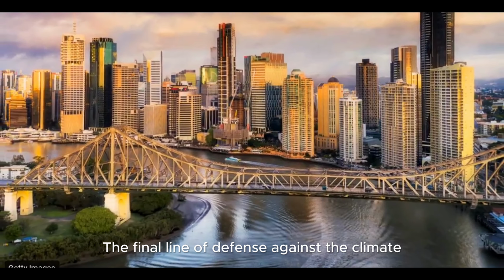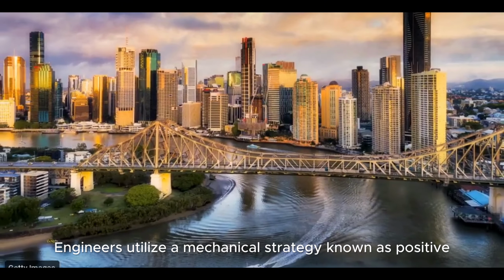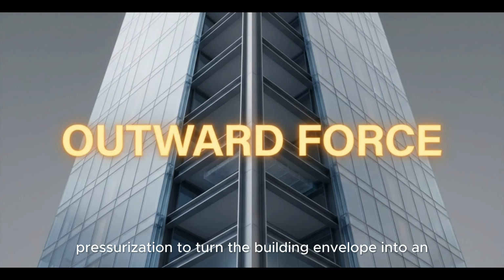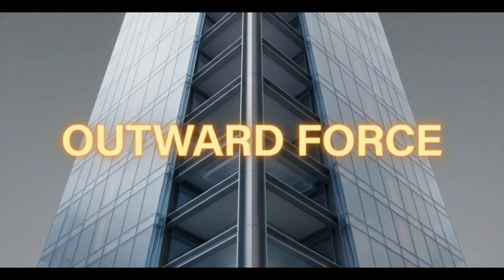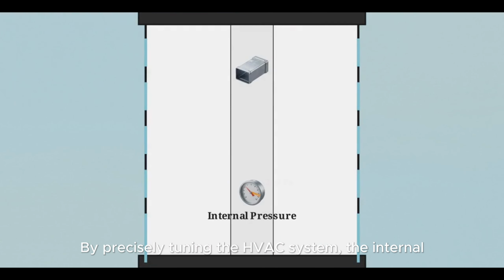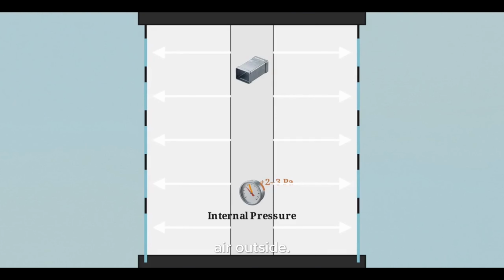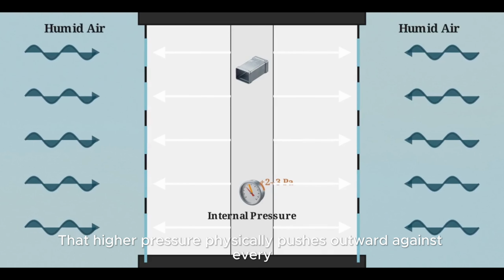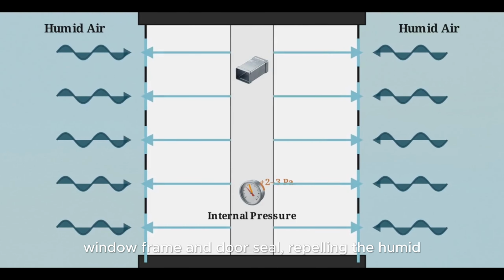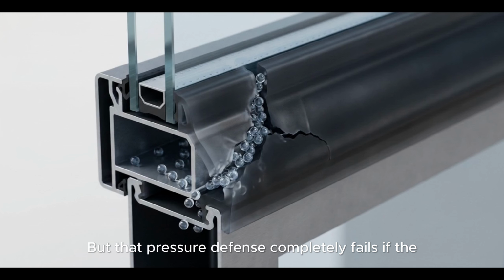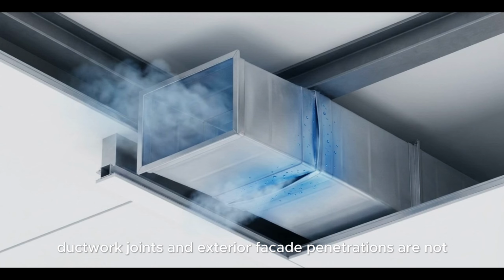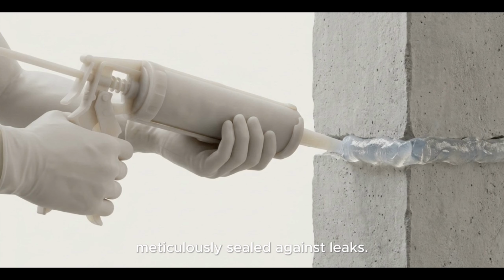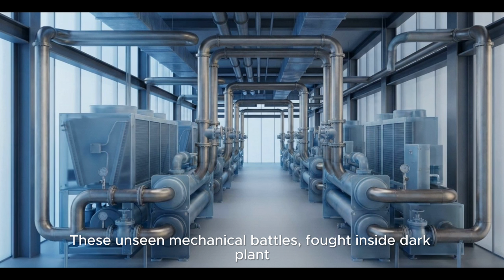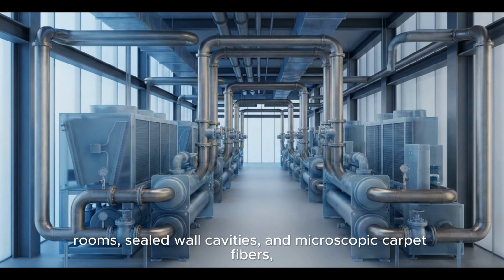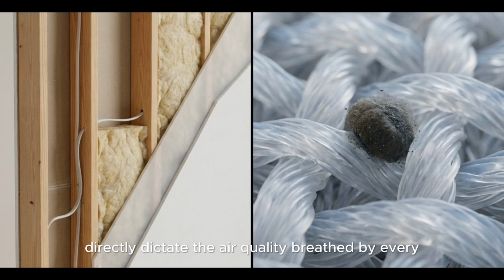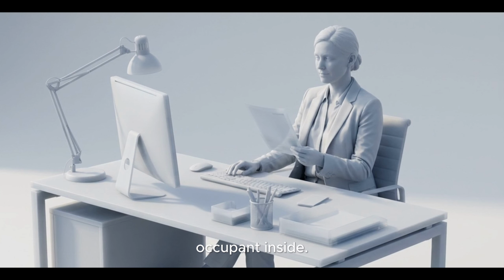The final line of defense against the climate is the skyscraper's outer skin. Engineers utilize a mechanical strategy known as positive pressurization to turn the building envelope into an active shield. By precisely tuning the HVAC system, the internal air pressure is kept slightly higher than the air outside. That higher pressure physically pushes outward against every window frame and door seal, repelling the humid air trying to seep in. But that pressure defense completely fails if the ductwork joints and exterior facade penetrations are not meticulously sealed against leaks. These unseen mechanical battles, fought inside dark plant rooms, sealed wall cavities, and microscopic carpet fibers, directly dictate the air quality breathed by every occupant inside.